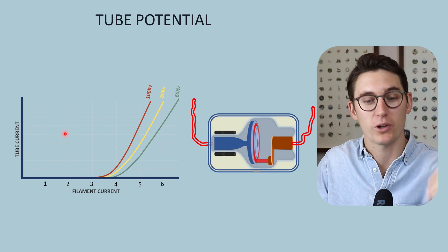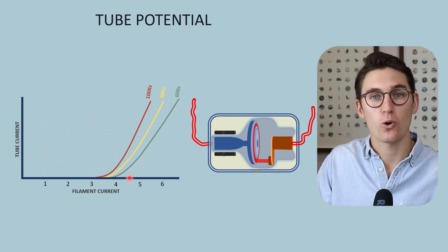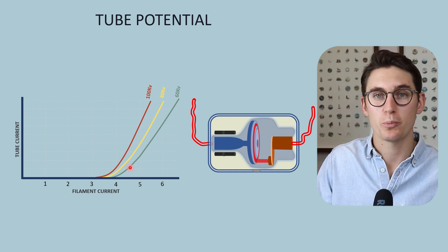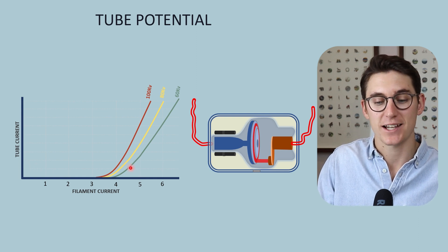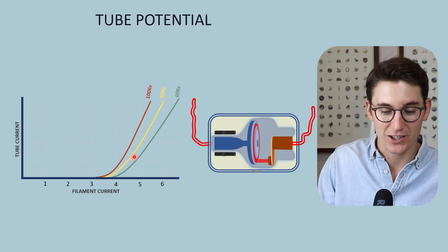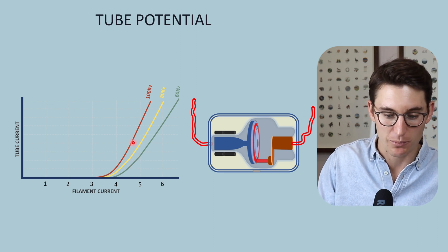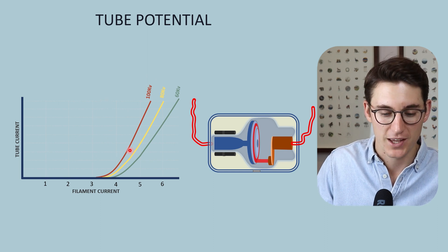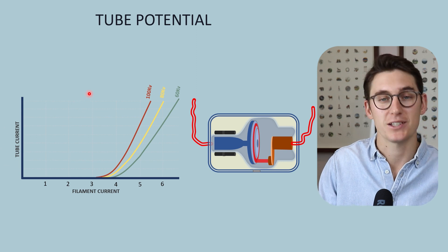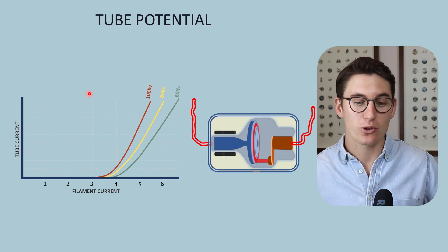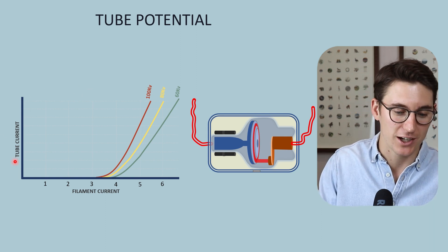At 4 mA, our 60 kilovolt tube potential results in a relatively low tube current. As we increase that kilovoltage to 80, we get a significant jump in tube current, and an even more significant jump when we go to 100 kilovolts. Our relationship between tube potential and tube current is exponential — an increase in tube potential results in an exponential increase in our tube current.